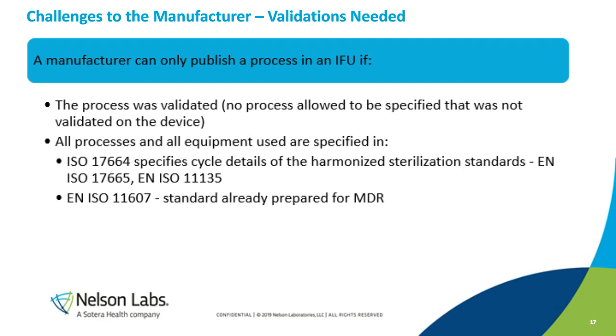I want to go into the fact that a manufacturer can only publish a process in the IFU if the process has been validated, and all processes and all equipment recommended in the IFU need to be specified according to ISO 17664, EN ISO 17665, EN ISO 11135, and EN ISO 11607. All of these standards need to be complied with when performing the validations for the processing instructions for a reusable medical device.